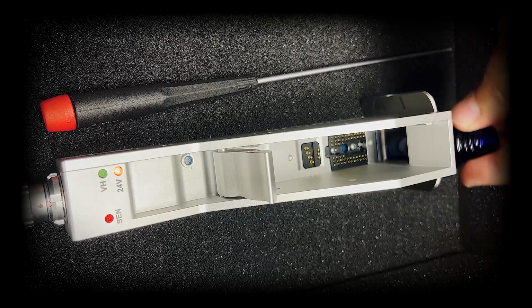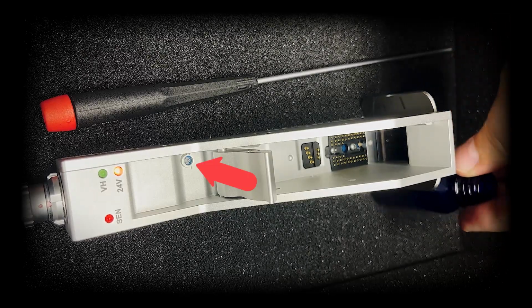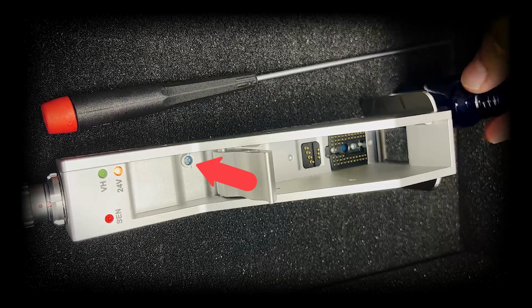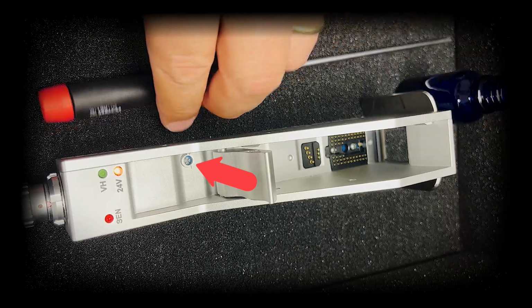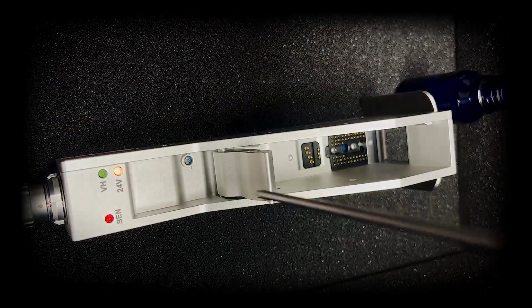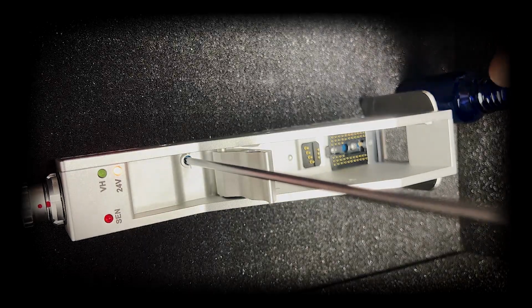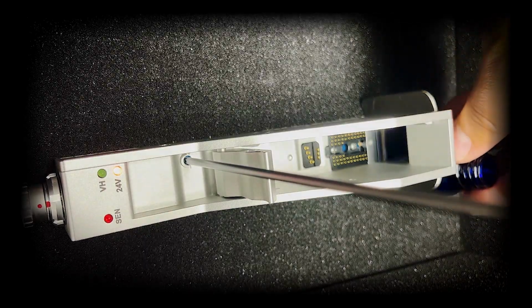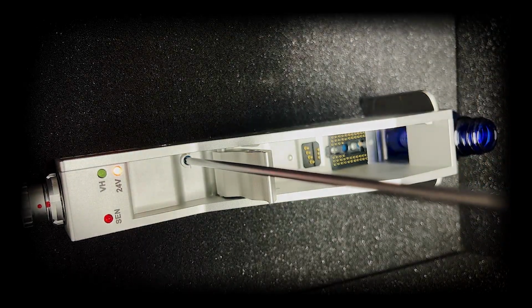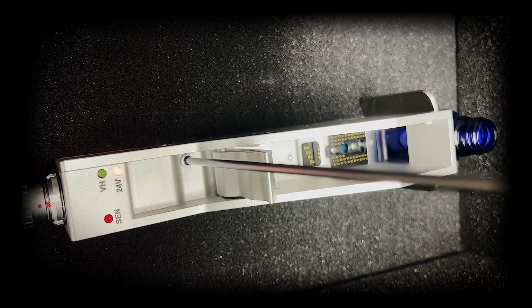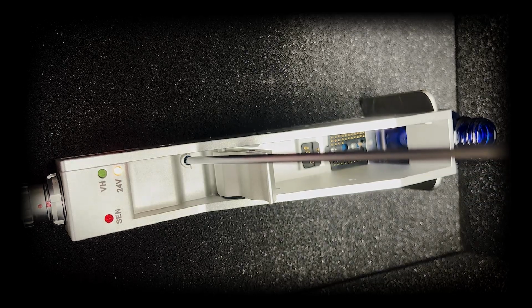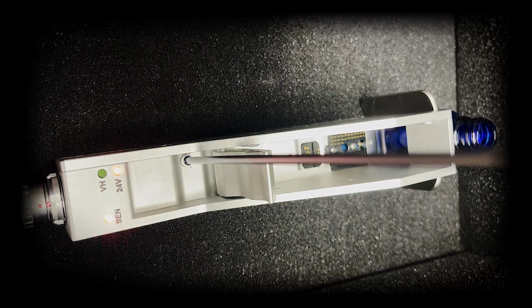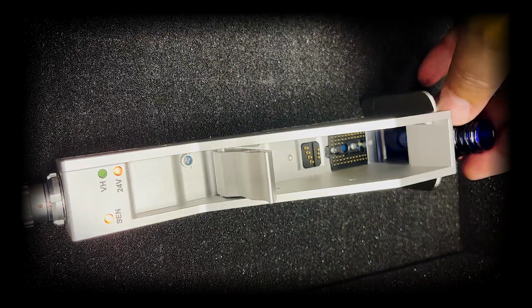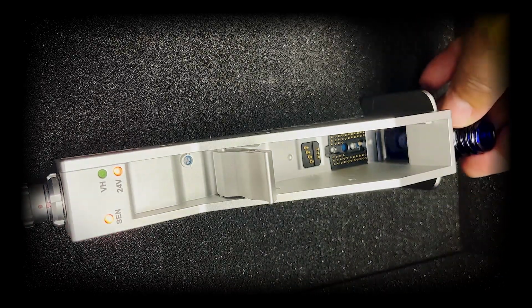On the back of the printhead, there's a small potentiometer screw for sensitivity adjustment. Use a size 0 Phillips screwdriver to turn the screw and fine-tune the sensor based on your product and environment. For best results, keep the printhead about 0.2 inches or 5 millimeters from your product. A well-adjusted sensor ensures consistent detection and print quality.